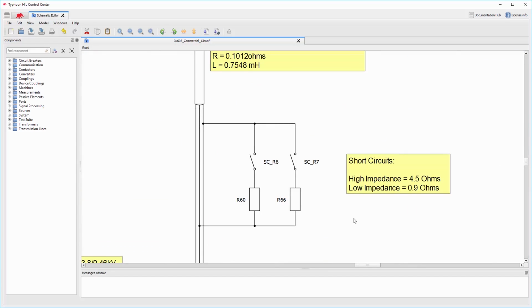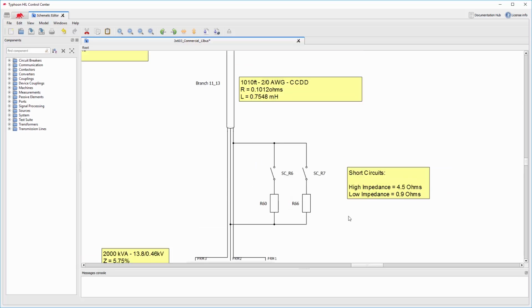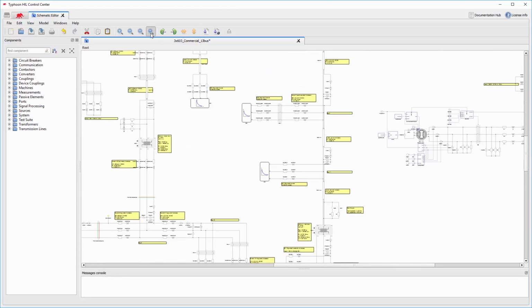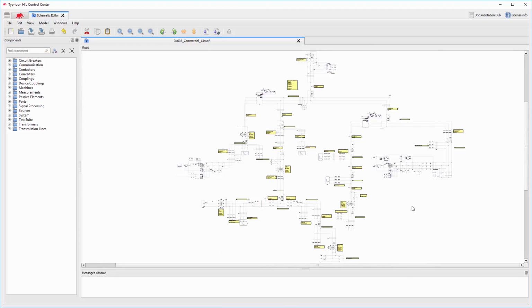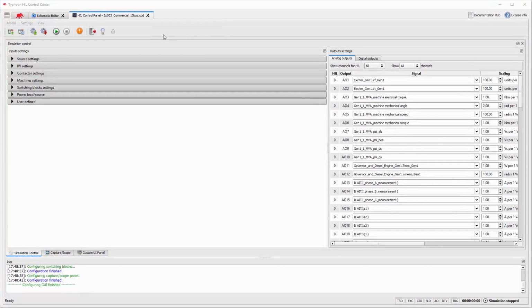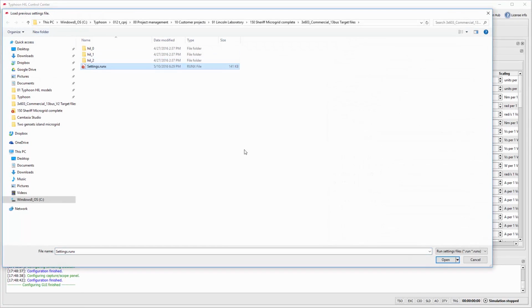To implement short circuits for fault analysis, we used single-phase contactors that, when closed, connect two phases together. We used an impedance in series with the contactors to regulate the level of the short circuit current. Once we complete the model with everything needed, we can compile and upload it in the HIL units by clicking one button. Now that the model is uploaded in the HILs, we can load the settings we previously saved.